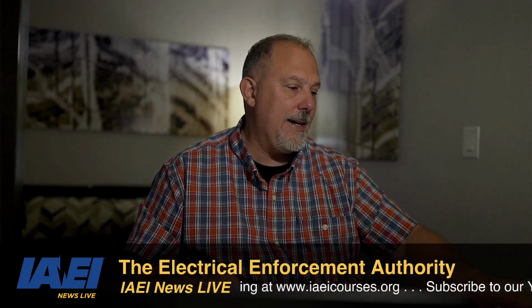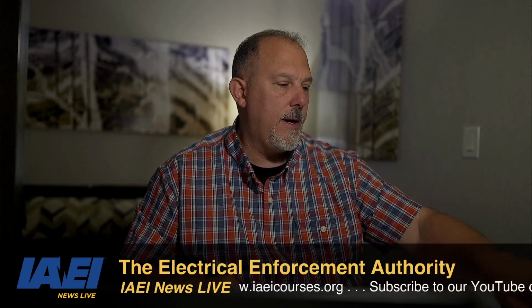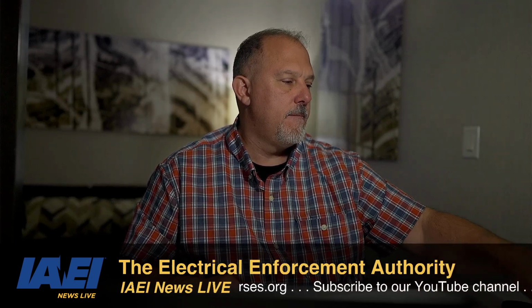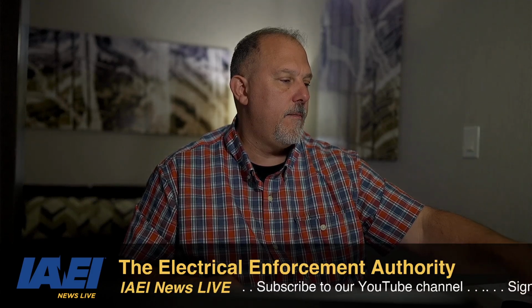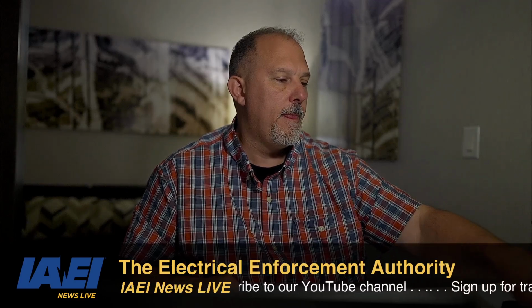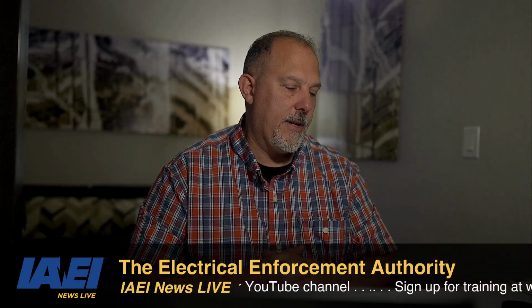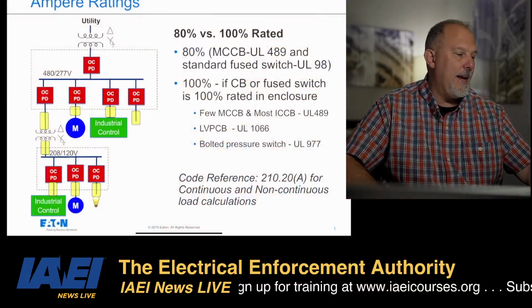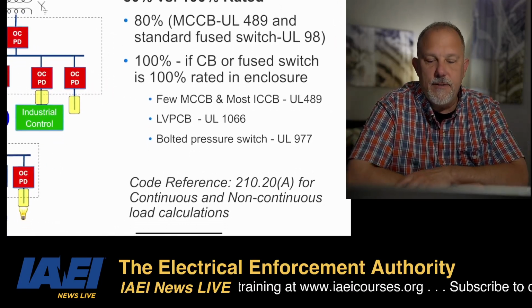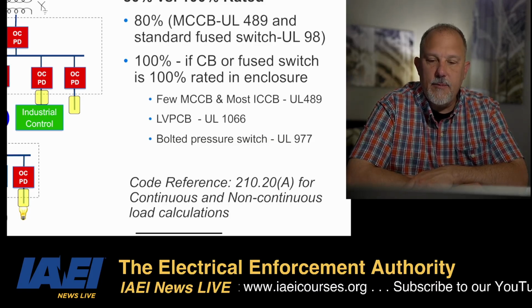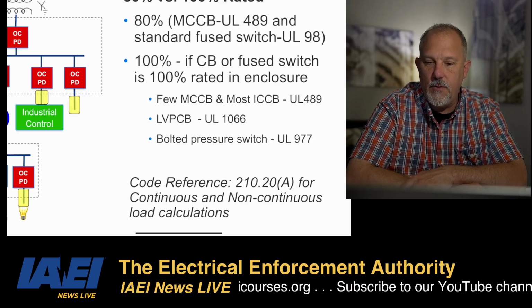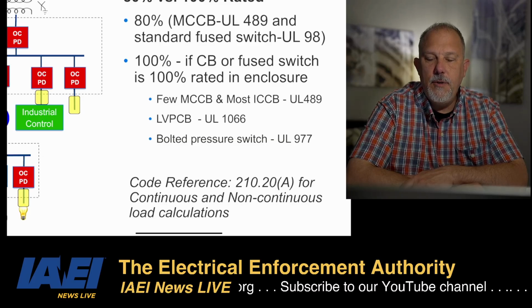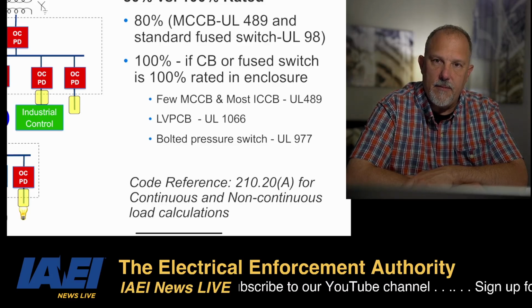I'm looking for, here it is. I think I found it. That label. All right. I'll explain this. I'm just going to show this. So let's say that I have a 100% rated breaker versus 80%. 80% is basically what you have every day of the week, twice on Sunday. If it's a 100% rated breaker or fuse, you need to think about UL 489, but you also need to think about the assembly.